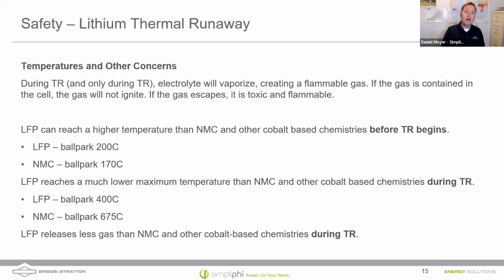Part of our 9540A testing is that we simulate that. What we've noticed is that it takes a higher temperature for LFP, lithium iron phosphate batteries, to reach thermal runaway. And when it does reach that event, it has a much lower maximum temperature than some of the cobalt-based batteries. Also, there's less gassing, partly due to the form factor, but also partly due to the chemistry.